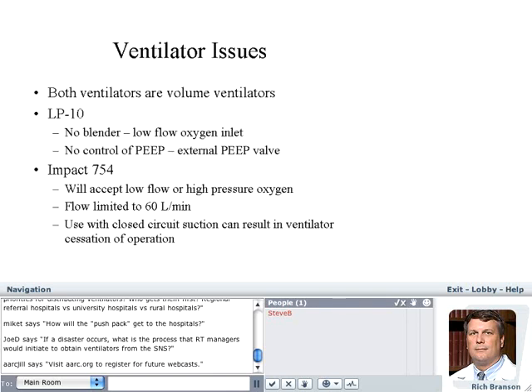The reason is the inlet for the compressor is the same size as the outlet for the circuit. And there was concern that, since this is a ventilator used in the military, if it were used in a stressful situation in the dark, somebody could hook it onto the wrong connector and you'd end up drawing gas out of the lungs. So what does this mean to the therapist? Any of you who've worked with this device, or some of the military people, know that sometimes you can get somebody who's very aggressively breathing during suctioning, and while they're taking in deep breaths and you're sucking the gas out, you'll meet that criterion of minus 10 centimeters of water pressure and the ventilator will turn off.